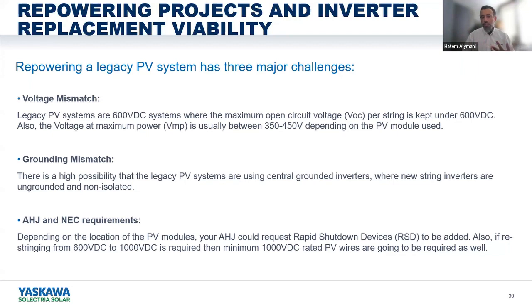So the 3 challenges: the voltage mismatch, as we said. Either the 600-volt modules, you're not going to be able to string them to 1,000 because they are rated for 600 volt. Maybe the wiring is also rated for 600 volt only. So that's the voltage mismatch. There's also grounding mismatch. Some of the older modules will require the modules to be either negatively grounded or positively grounded, and our inverters are ungrounded inverters. So that's also going to create some issues and some challenges. And the last thing is the AHJ requirement and NEC requirement. Some of the AHJs will require you to retrofit rapid shutdown devices there. So that's something also to consider.